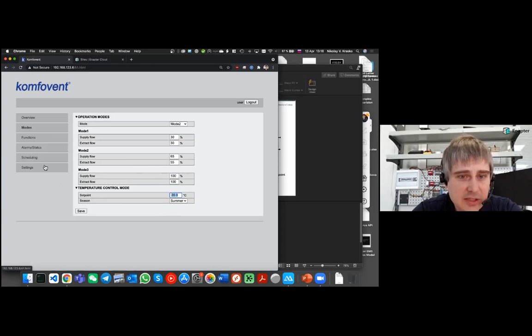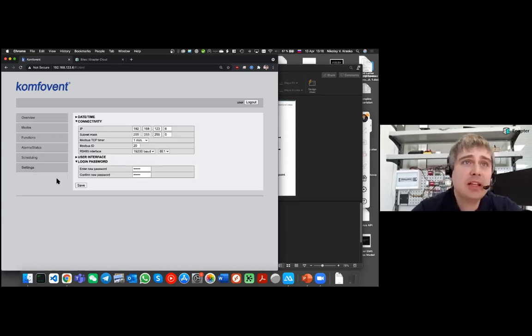Okay, so this is the data which we can get from the system. The last very important setting we need to check is a connectivity. Because we are using the RS485 interface, we need to check the connection settings because they need to be the same on both sides. So here we need to write down that the Modbus ID slave is 20, and the RS485 interface settings are: speed is 19,200. We have 8 data bits. The parity is even, and 1 stop bit. So we need to save this data because we will later use it.